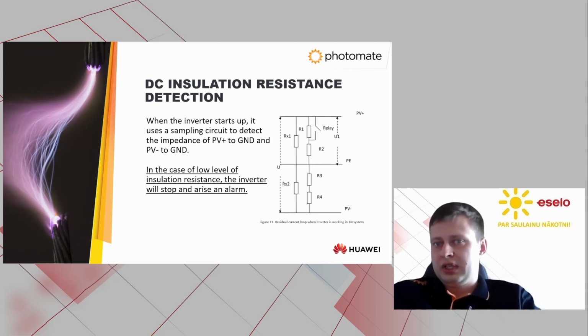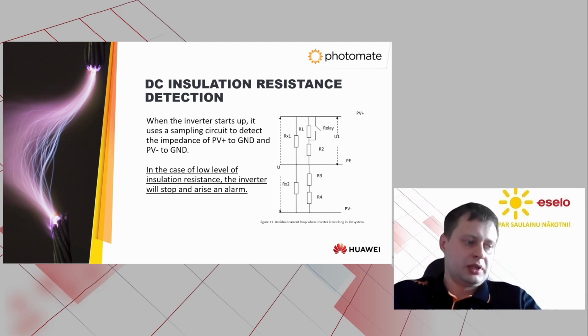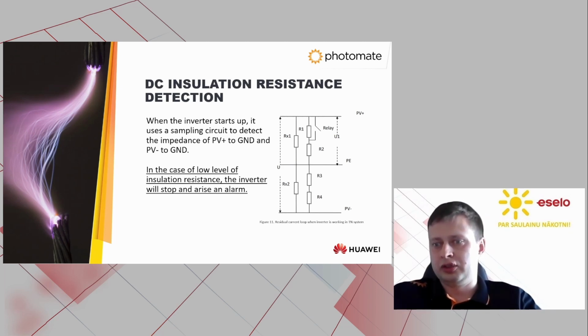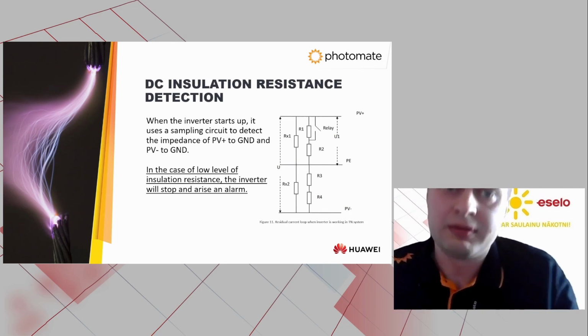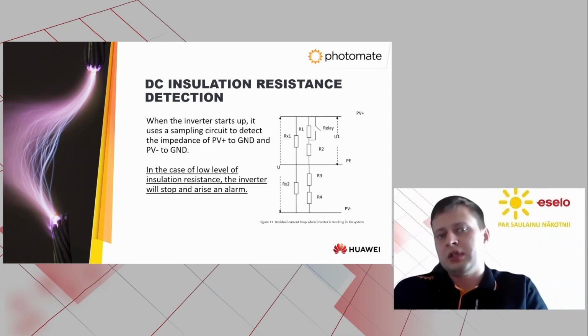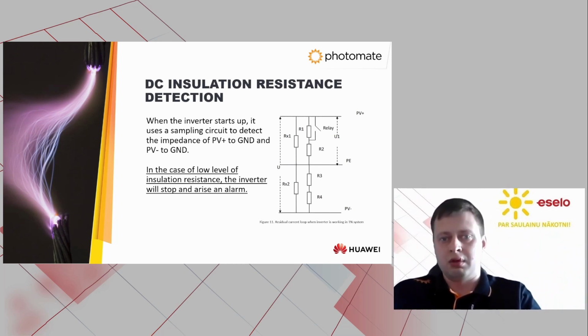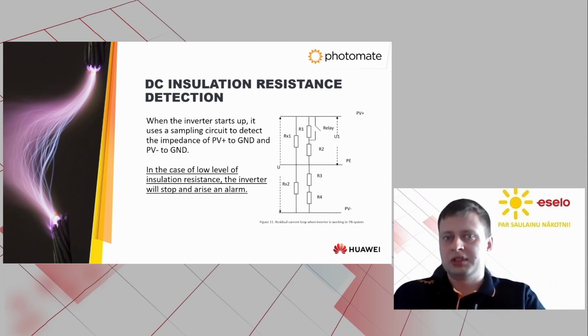To ensure the safety and proper functioning of PV systems, basically all transformerless inverters deploy DC insulation resistance detection. During every startup of the inverter, every morning before the startup, this function checks the insulation resistance level. And in case something is wrong, it does not allow the inverter to start, to avoid leakage, short circuits, etc.